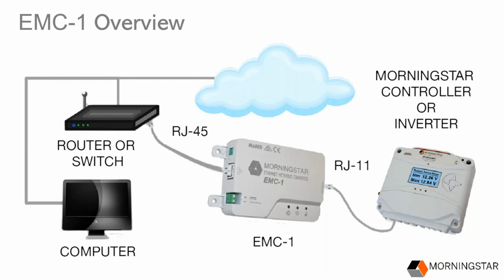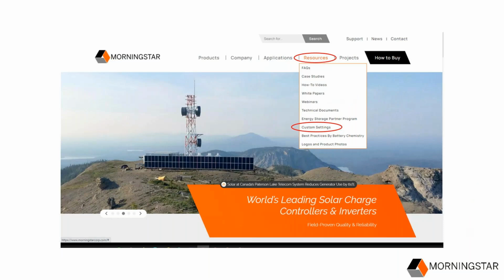Furthermore, you can use our free MSView software with the EMC to change your battery charge settings, low voltage disconnect settings, and lighting settings. Every product in MSView has its own setup wizard for adjusting these settings. To make the wizards easier to use, we've created a web page that lets you download pre-made custom setting configuration files. If you click the resources tab on our website and then custom settings in the dropdown, you'll access a page with links to product factory preset configuration files for all our applicable controllers. You might only need to change a few settings to match your battery brand and type, so these preset files can save a lot of time versus entering values manually.